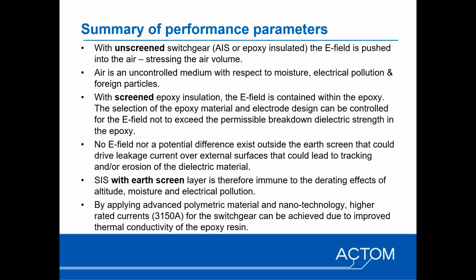In summary, with the unscreened switchgear, typically AIS, and even unscreened epoxy insulation, the electrostatic field is pushed into the air, stressing the volume of the air. The air is uncontrolled as a medium with respect to moisture, electrical pollution, and foreign particles. Whereas with screened epoxy insulation, the electrostatic field is contained within the epoxy, and by selecting your epoxy material properties and your electrode design on the inside of that epoxy, you can actually control the electrostatic field appearing, so as not to exceed the permissible breakdown strength of the epoxy.